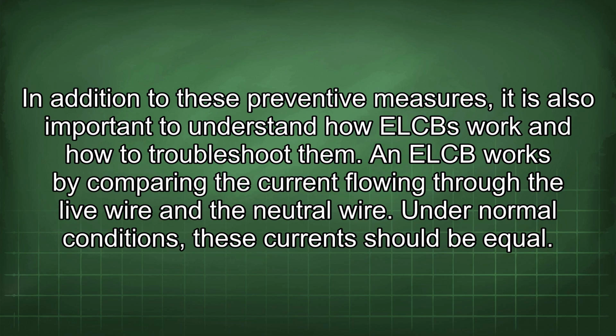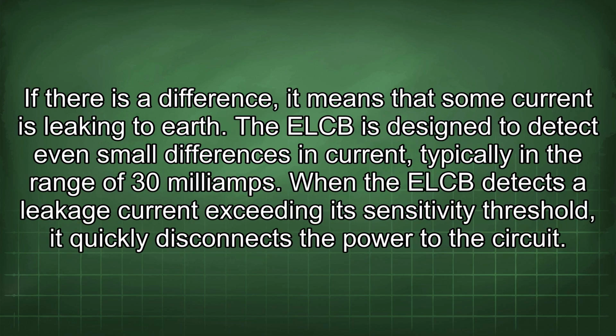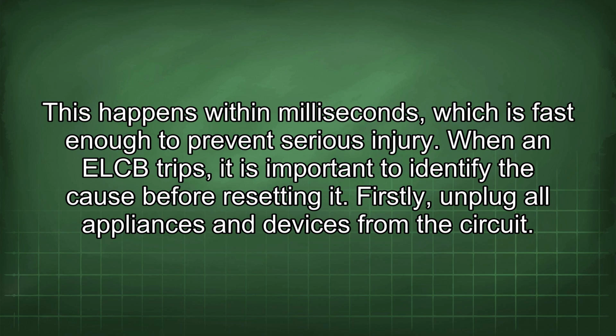An ELCB works by comparing the current flowing through the live wire and the neutral wire. Under normal conditions, these currents should be equal. If there is a difference, it means that some current is leaking to earth. The ELCB is designed to detect even small differences in current, typically in the range of 30 mA. When the ELCB detects a leakage current exceeding its sensitivity threshold, it quickly disconnects the power to the circuit. This happens within milliseconds, which is fast enough to prevent serious injury.